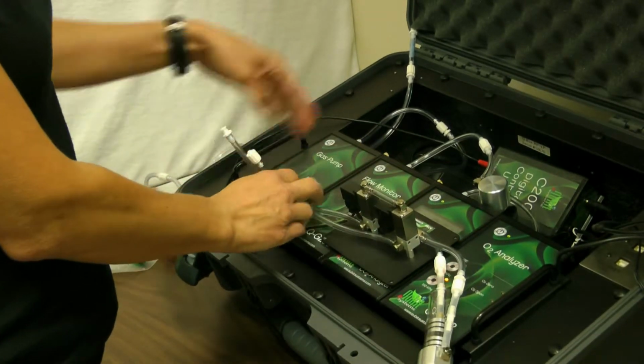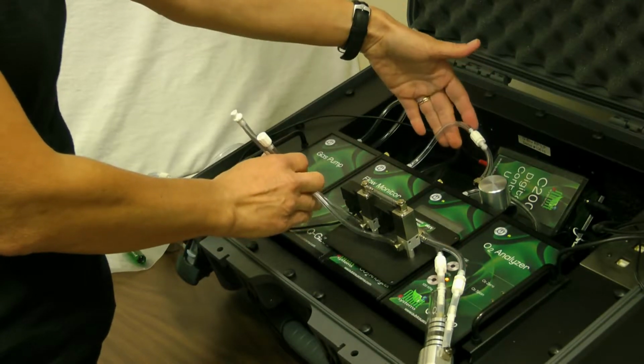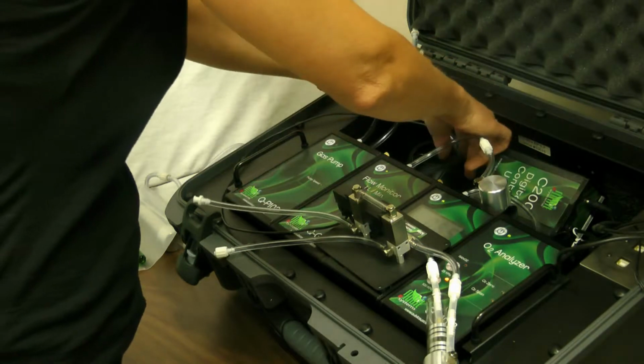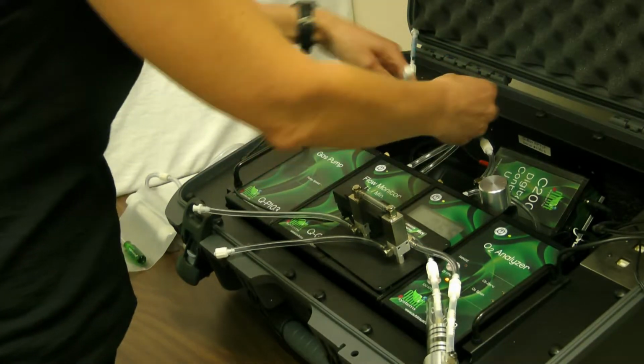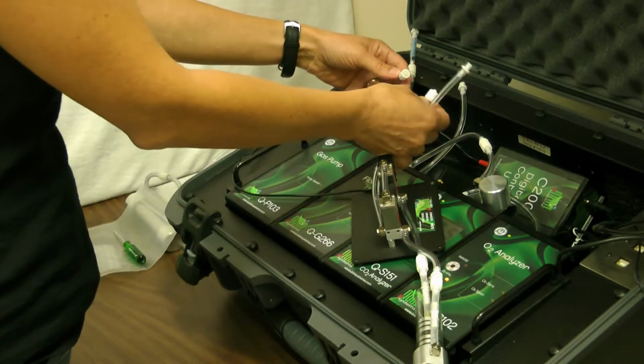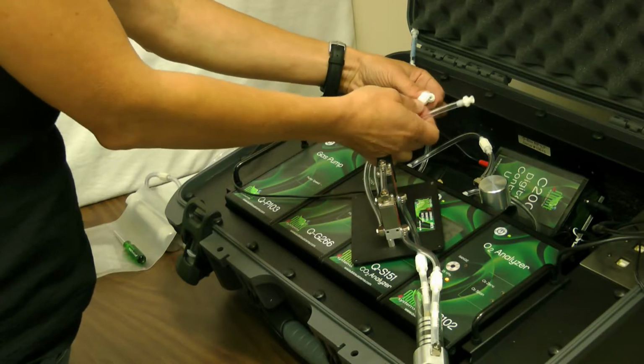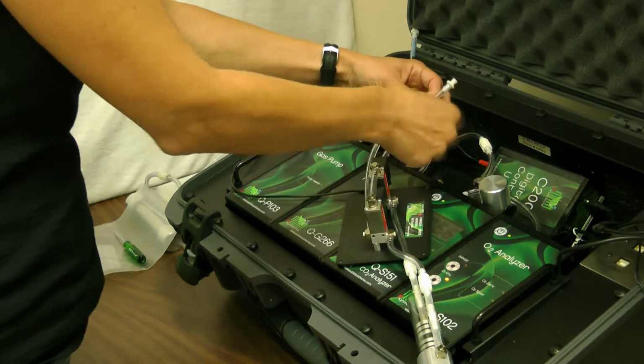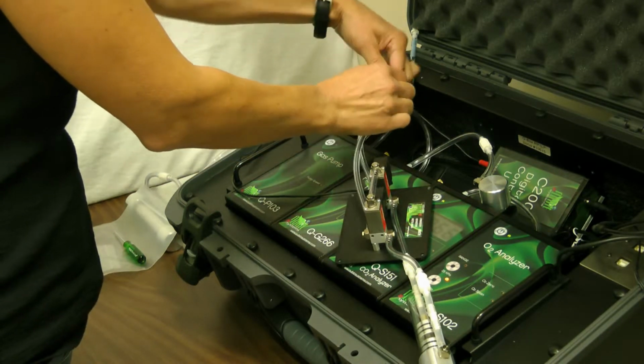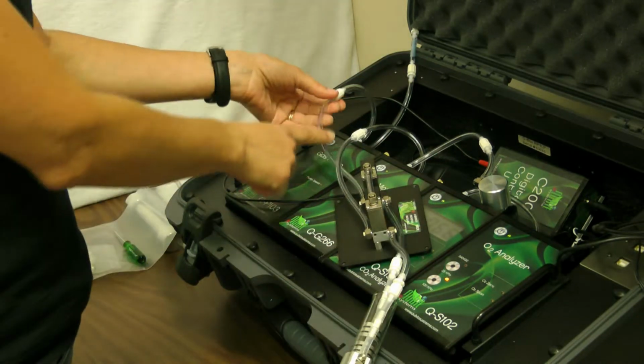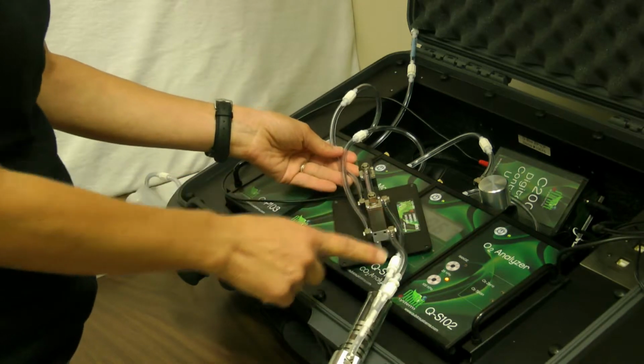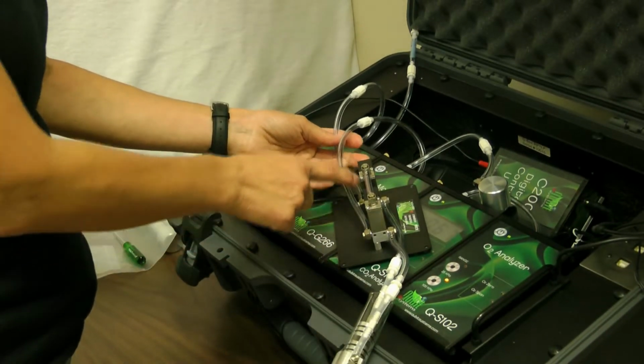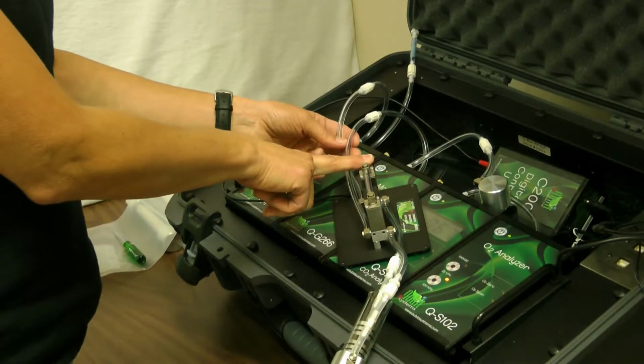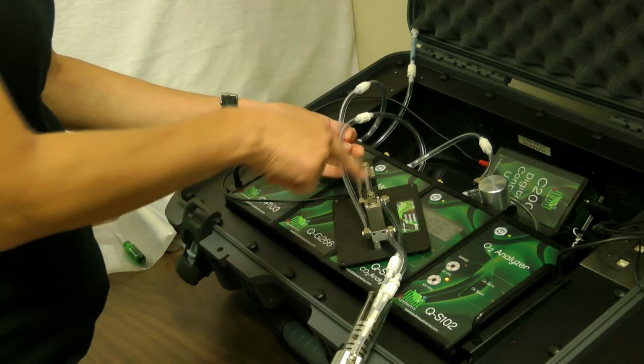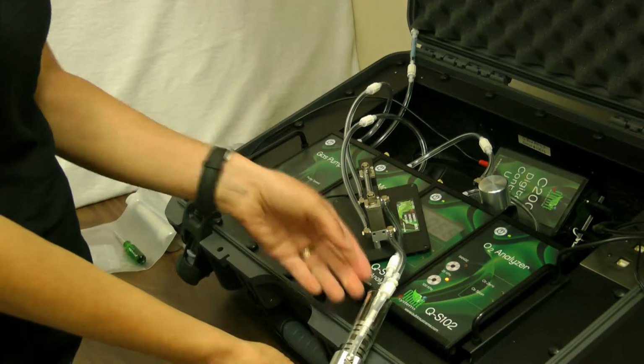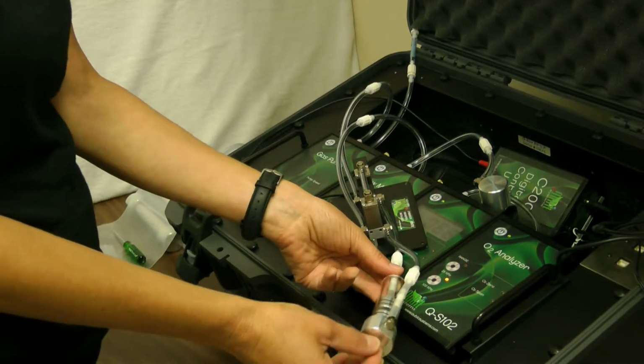So after your calibrations, when you have this setup that I've explained for a standard package, you can disconnect the gas pump and the flow monitor and attach them to the two pieces of tubing coming from the solenoid. And again, you cannot mess up because they are male to female and female to male connectors, luer connectors. So you have the gas pump supplying the gas to the solenoid valve. From the solenoid valve, it goes into your chamber, out of your chamber, through the solenoid valve, and to the flow monitor. And when the valve is activated, then the gas bypasses the chamber and it just goes directly to the system, and the chamber at that point in time is in stop flow mode.